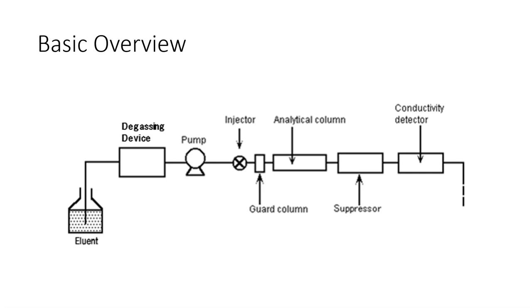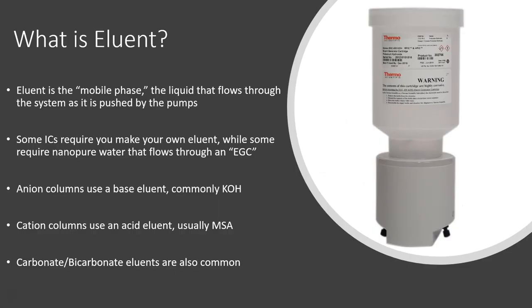First let's talk about the eluent. What is eluent? Eluent is the mobile phase—this is the liquid that flows through the system as it's being pushed by the pumps. Some ICs require that you make your own eluent, while some require nano pure water that flows through an EGC. EGC means eluent generator cartridge, which uses an electrolytic chamber to turn very concentrated eluent into a more diluted eluent based on a current that you apply to it. That's what this picture is on the right—this is an EGC.